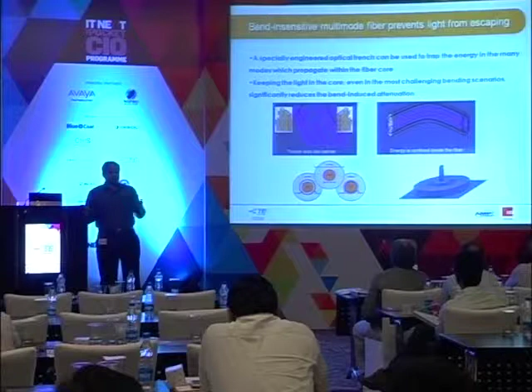Now customers also started looking at single mode, fine, we go for bend insensitive. Why not multi-mode? Look at each of your data centers. The first rack which is highly densely populated is your storage area networks. You have high density of fibers coming onto your SAN. You will not even remove one fiber patch cord from your SAN when doing adds, moves and changes, because you don't know which one you're pulling out. It's better to put it on the next port and connect an additional one rather than remove the existing one. So bend radius management is also becoming critical within your DC environment on the racks.